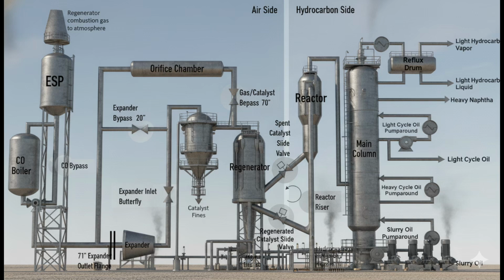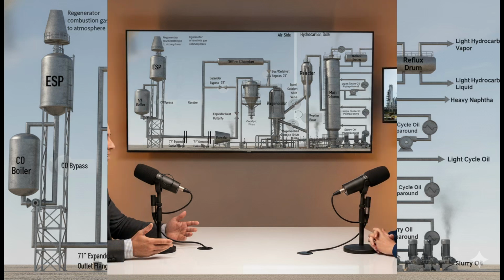And the ignition point for that explosion was the very last piece of equipment on the air side, a device called the Electrostatic Precipitator, or ESP. Let's unpack that, the ESP, because its normal function is just so key to understanding why this was guaranteed to happen once the leak started. It's actually a pollution control device. It is. Its whole job is to remove these tiny microscopic catalyst particles from the combustion gases before they get released into the atmosphere, to meet air quality rules. But the way it does this is the critical hazard here.